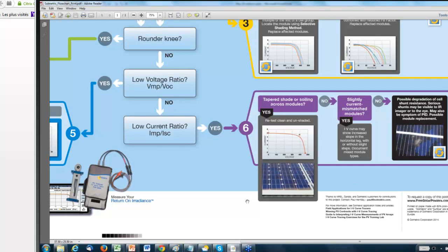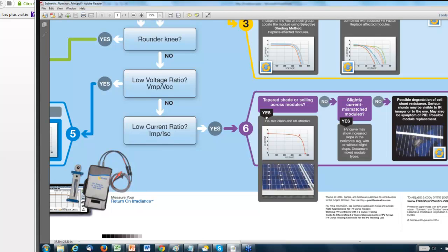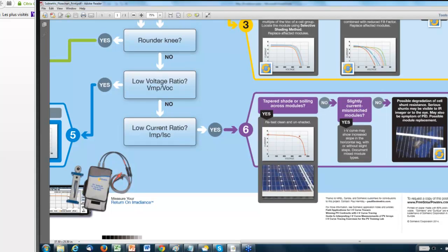And sometimes you'll see this across your whole system. The dirt band can increase continually across the array, or it can be just repeated from module to module and have the same effect. If you clean off that dirt band, this IV curve will snap right back up to where it should be.